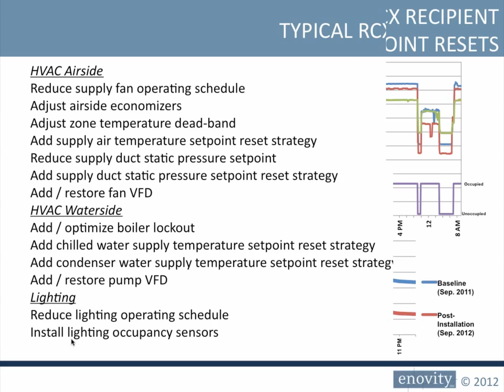Here's a case study for a combination lab and office system that we just recently worked on. You can see it's just last month. Looking at the top half of the screen, you've got the before on the left and the after on the right. They had lab spaces that need air all the time, but they had office areas that didn't need air all the time. So basically what was implemented was an occupancy schedule for the VAV boxes that serve the offices.